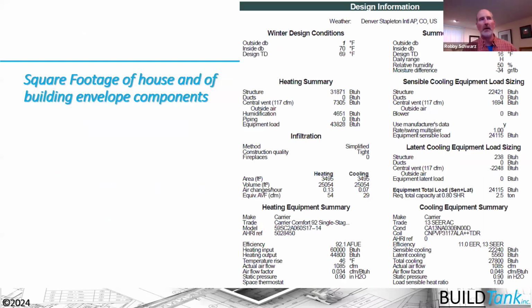So the next one I want to talk about is the square footage of the house. Doing a takeoff of a house and entering the results, the square footage of all our building components into a Manual J calculation is not necessarily a simple process. And every person is probably going to get slightly different results. And that's okay within reason. If you're within 10 to 20% of each other there, then you're going to be okay. You're going to have a pretty sound Manual J heat load calculation.